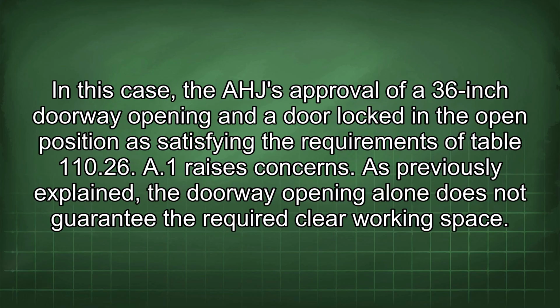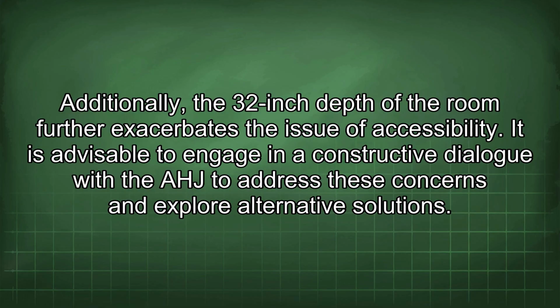In this case, the AHJ approval of a 36-inch doorway opening and a door locked in the open position as satisfying the requirement of Table 110.26(A)(1) raises concerns. As previously explained, the doorway opening alone does not guarantee the required clear working space. Additionally, the 32-inch depth of the room further exacerbates the issue of accessibility.